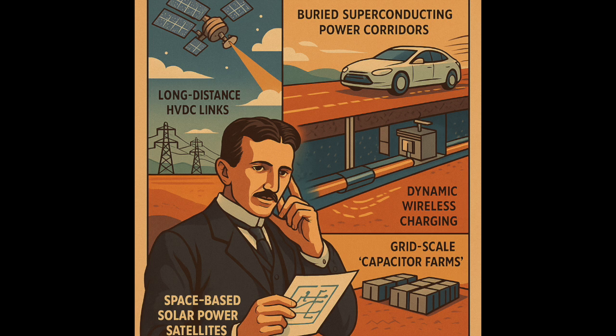That's where HVDC comes in, high voltage direct current. It's really the complementary technology for long-haul transmission. How does it differ from standard AC, alternating current? The key advantage is lower line losses over very long distances. AC systems inherently lose more power due to factors like inductance and capacitance, especially over hundreds or thousands of miles. HVDC avoids a lot of that, and it eliminates reactive power issues.